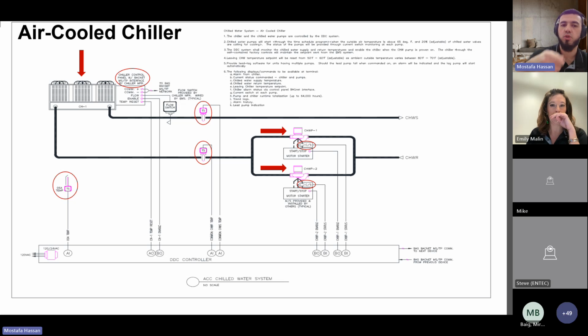That is your best bet because you're running one wire. If you run an 18/4 and just hardwire it, but you're not collecting anything from the BACnet interface, you're actually missing out on points, right? Also, when you do it through the VFD, it shows up automatically as a BACnet point on your system, right? So if you have a front end or an operating workstation, the VFD will show up if it has a BACnet interface. So that helps in programming. It helps in running your sequence of operations.